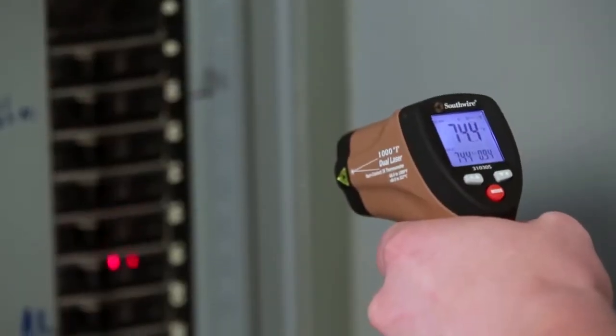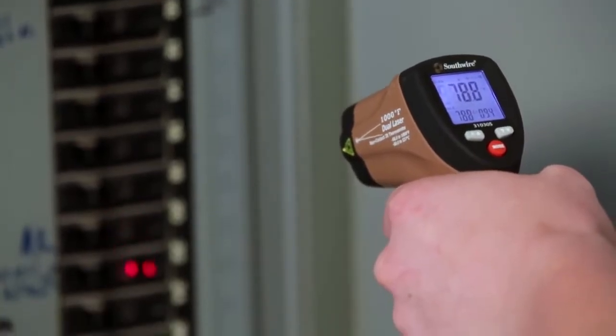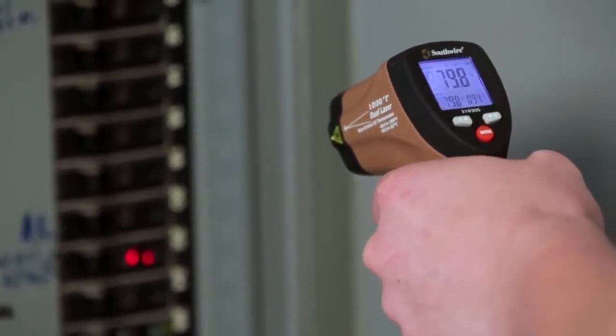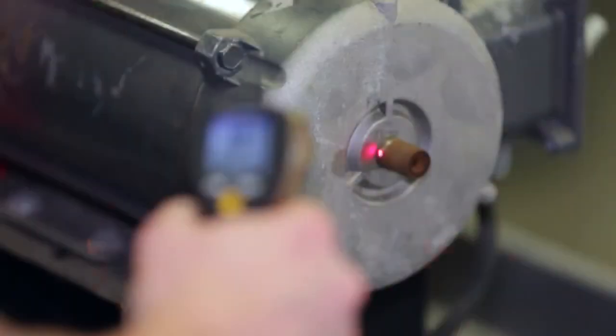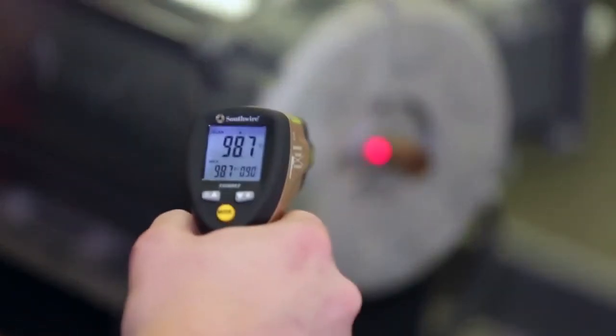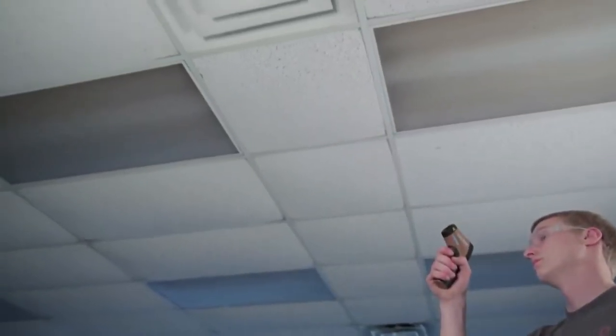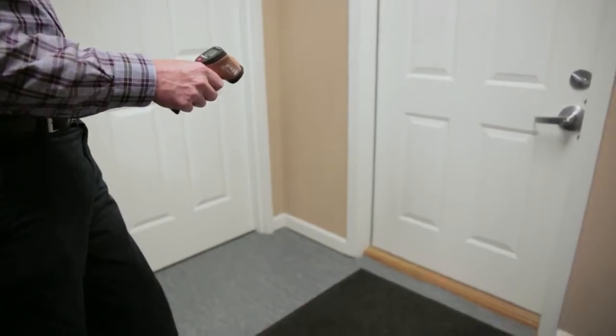They can be used to find hot spots in electrical panels caused by loose or corroded connections, locate fuses, circuit breakers, transformers, and other electrical devices that may be overloaded, check motors for overheating, detect worn bearings, and find all sorts of mechanical faults due to excess friction. They can check air conditioning ducts to make sure every room is getting cold air. They can be used in energy audits to locate missing insulation or poorly sealed doors and windows.